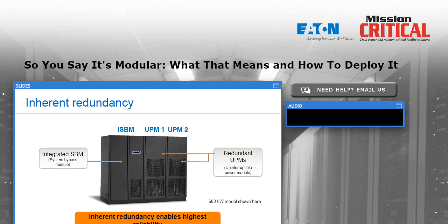So each one of the UPMs on the right-hand side is good for 300 kilowatts of capacity. So the client may elect to go ahead and deploy both of them in their original installation. That means as long as the critical load on this date and time is less than 300 kW, the system is already N+1 redundant. If UPM2 has a problem or needs to be shut down for maintenance, for example, UPM1 does not have to shut down at the same time.